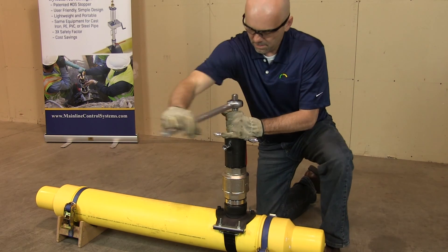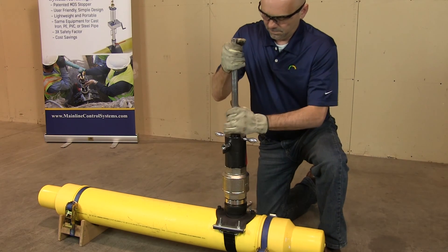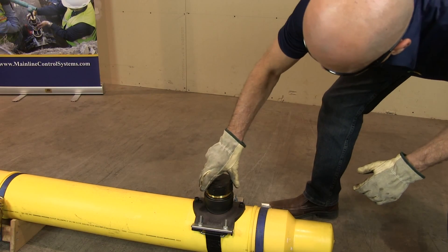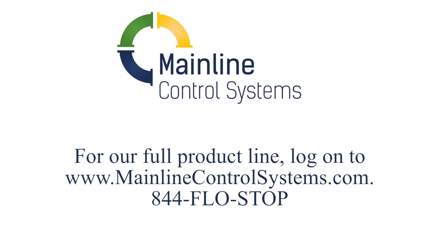Open the ball valve and lower the plug. With the hand ratchet, screw the plug into the fitting until bottomed out and tight. Test to make sure there is a seal. After the plug seal has been verified, remove the dome, valve, and valve adapter from the fitting. Inspect the completion plug for any leaks. If everything looks good, screw on the cap and your job is now complete. Be sure to consult the manual for full instructions. For additional information, contact Mainline Control Systems at 844-FLO-STOP or visit MainlineControlSystems.com.